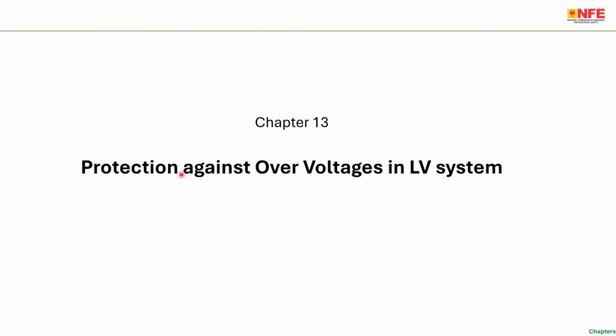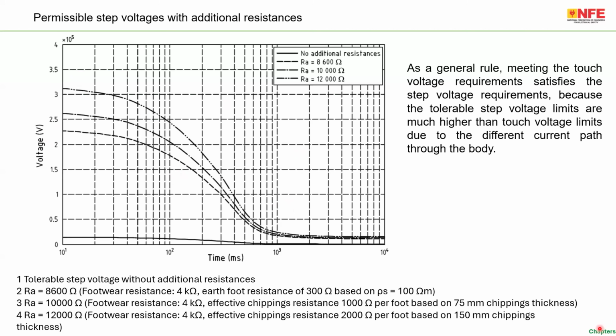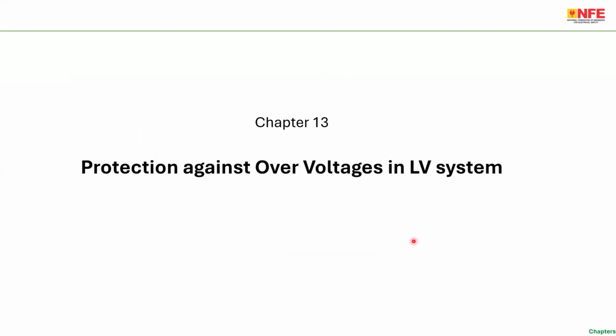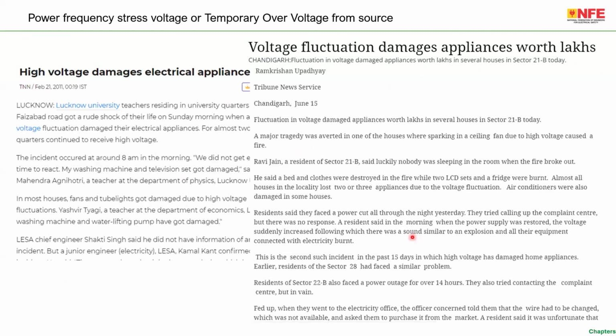I'm showing you this as an example. Coming back, the second subject which also has to be considered in case of a fault in an 11 kV or 33 kV system is failure of electronic equipment in the consumer premises. These are two news items from the newspaper. High voltage damaged electrical appliances. Voltage fluctuation damages appliances worth lakhs. Such news is quite common in our country.